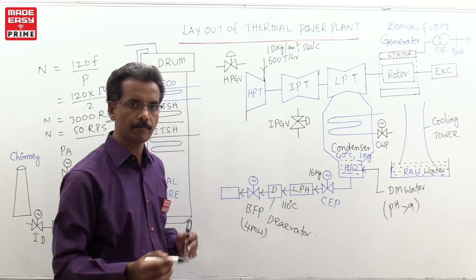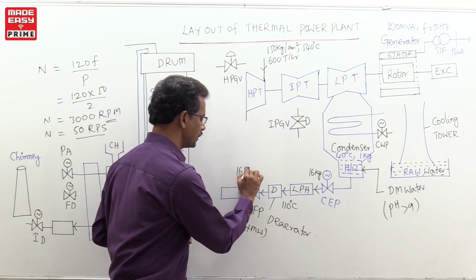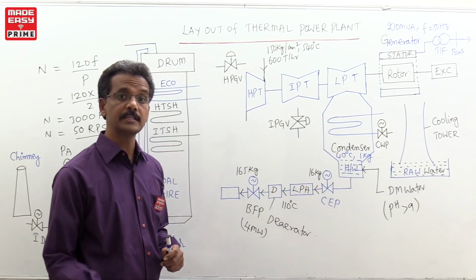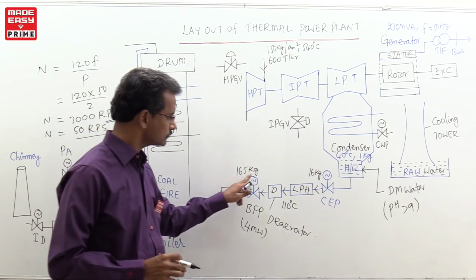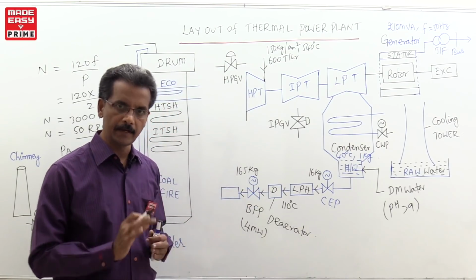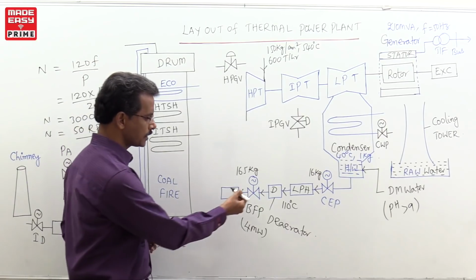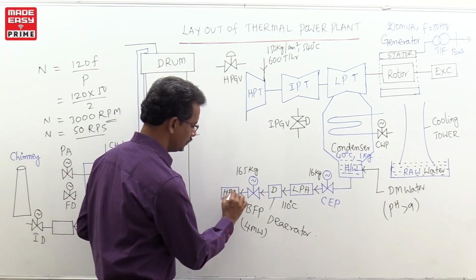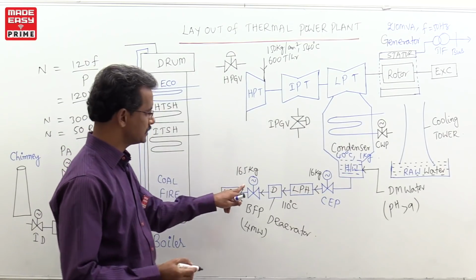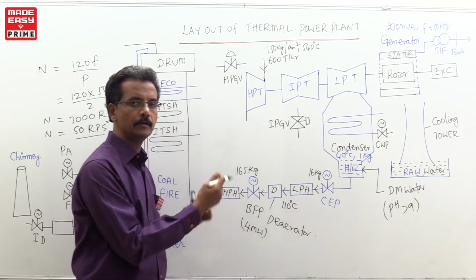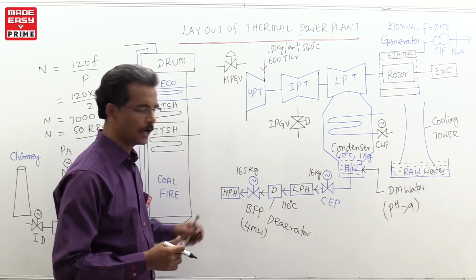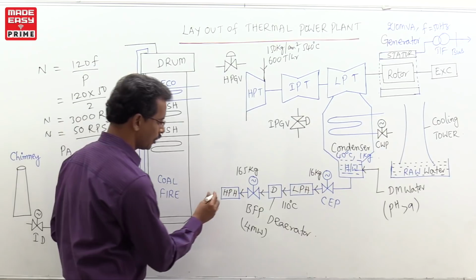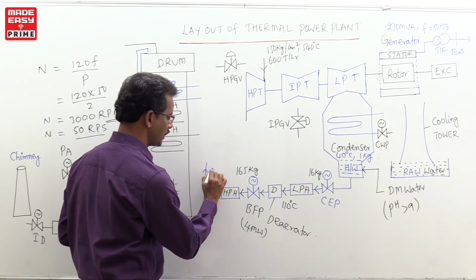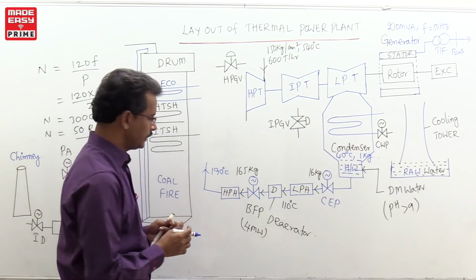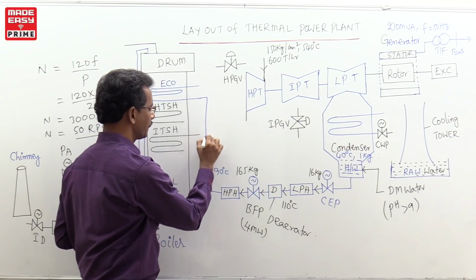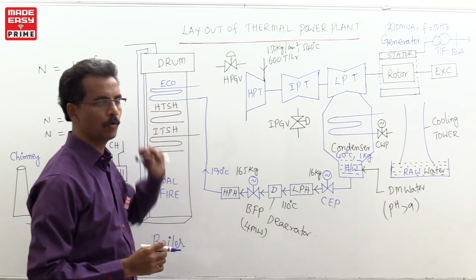The purpose of this boiler feed pump is increasing the pressure of the water. It will raise the pressure of the water up to 165 kg. This is the highest pressure generating pump in a thermal plant. So, this 165 kg of water pressure is entering into the high pressure heater. The high pressure water is heated by this high pressure heater, and the output is around 180 or 190 degrees centigrade, right. This water is sent to the economizer, this ECO, nothing but economizer.